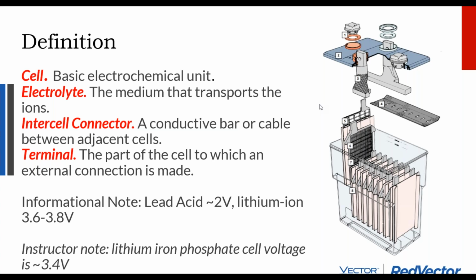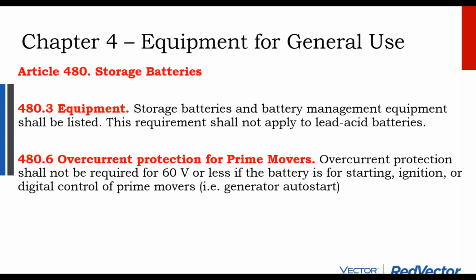And what that means is you'll have different voltage charge settings, with lithium iron phosphate being a little bit lower voltage. So we will have a 2-hour program just on those nuances, more of a design program later on, but this is our electric code class, so let's stick to electric code. So section 480 is kind of what the traditional battery section was before we start getting into higher voltage batteries. Commercial batteries can be 400 volts, 500 volts on up, even into 800 volts. So section 480 is more general battery requirements, and it is then expanded on later on. So let's learn the general requirements, then we'll get to the more advanced section towards the end of the program.